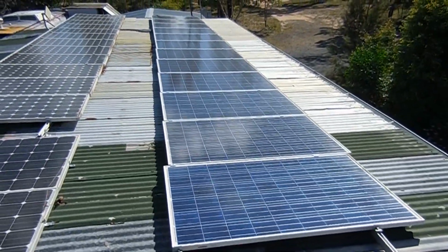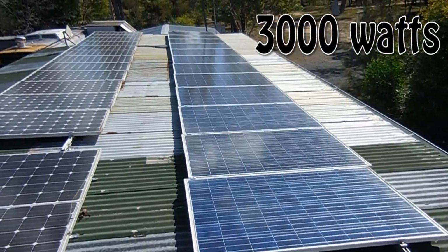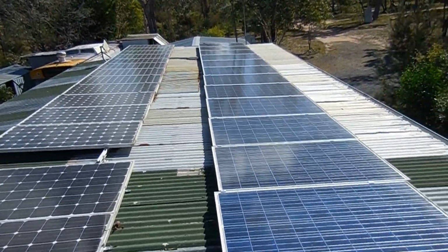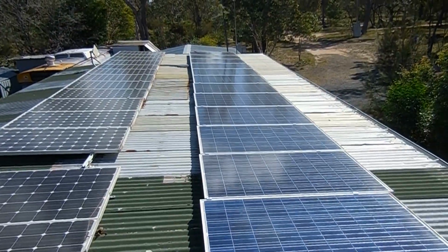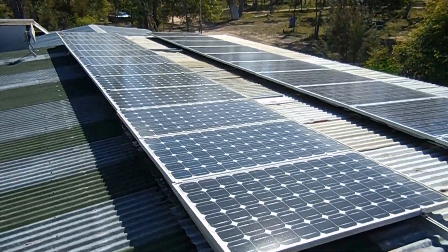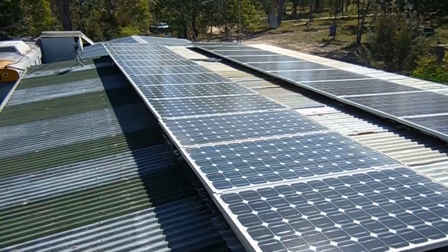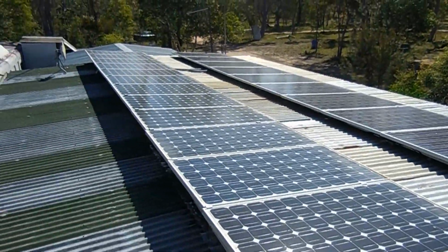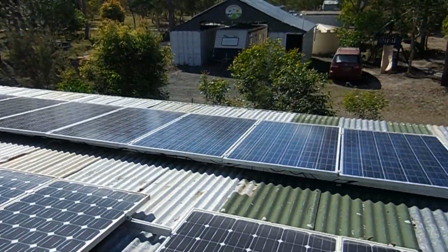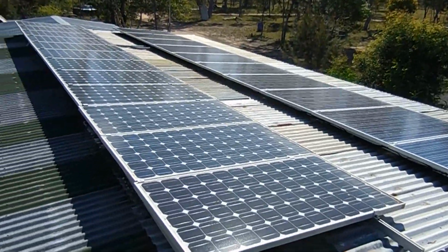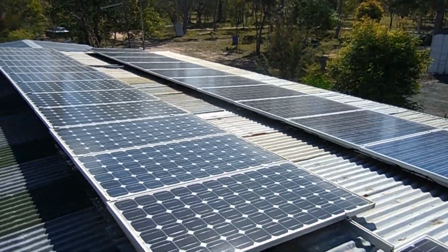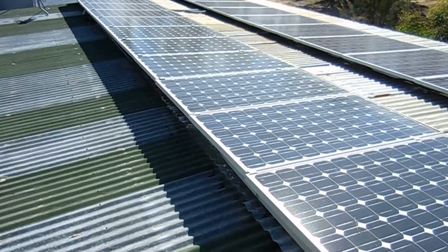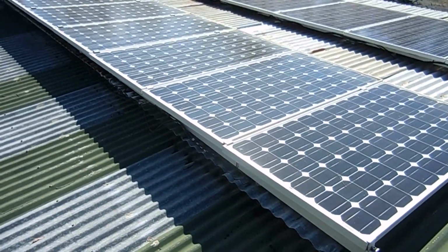We added another 3 kilowatts on the front to have a total of just over 5 kilowatts of solar input on the roof. In each set of panels we have 12 panels each. So we've got 12 panels in this 2 kilowatts and another 12 panels in that 3 kilowatts. These are 190 watt panels, they're 250 watt panels. The panels are wired in sets of 3.